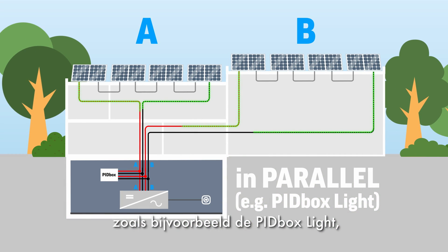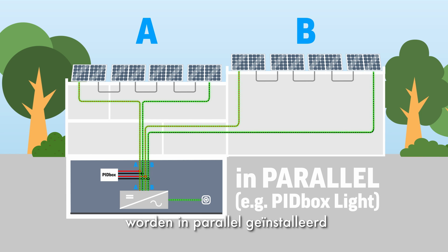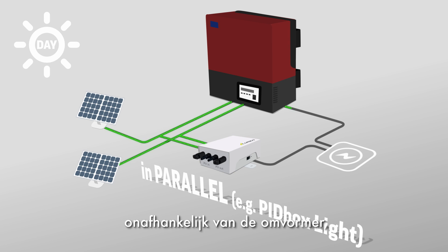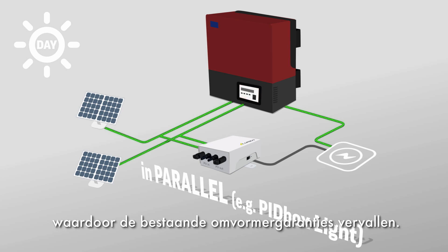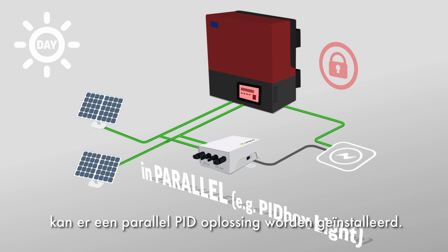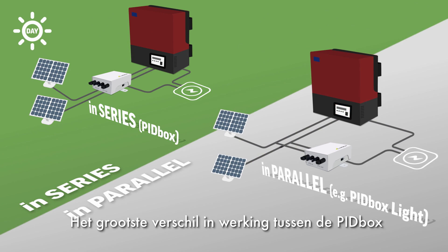Other PID solutions in the market, like for example the PIDbox Light, are connected in parallel between the solar panels and the inverter. These devices do not work independently of the inverter, which will cause inverter warranties to be void. A parallel PID solution can only be installed with permission of the inverter manufacturer.